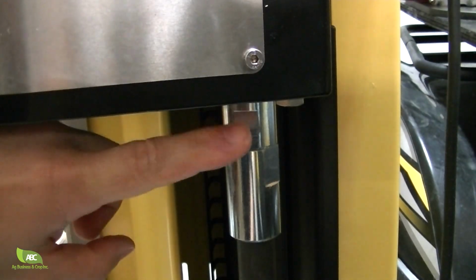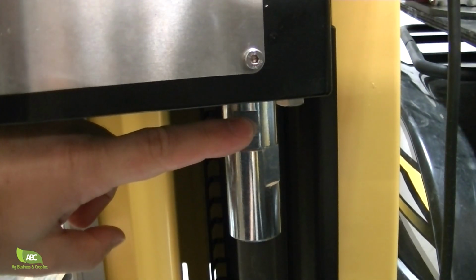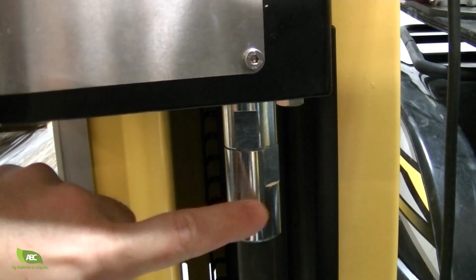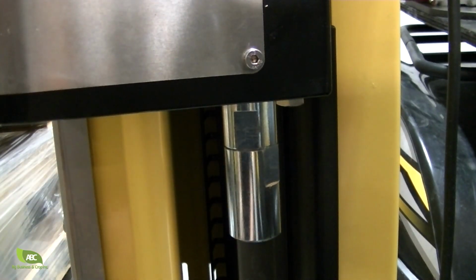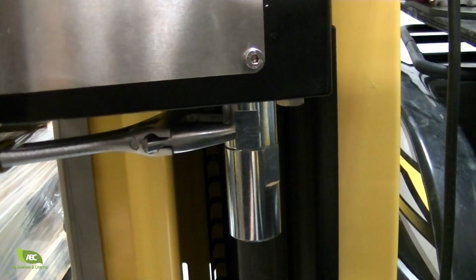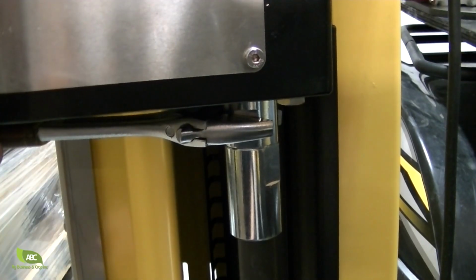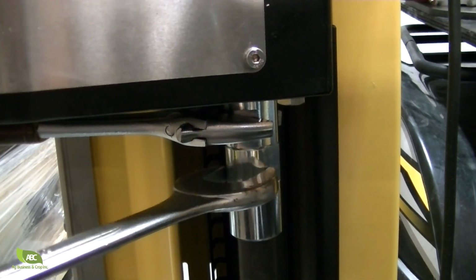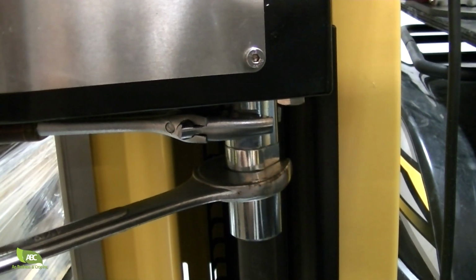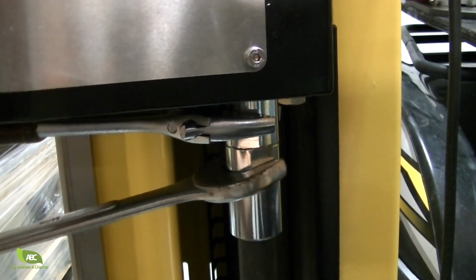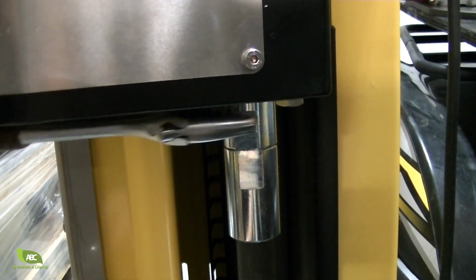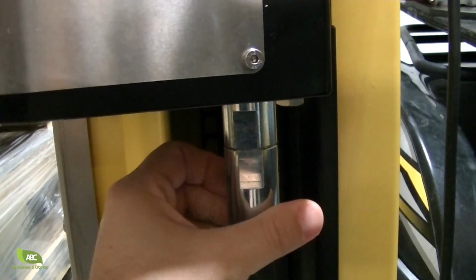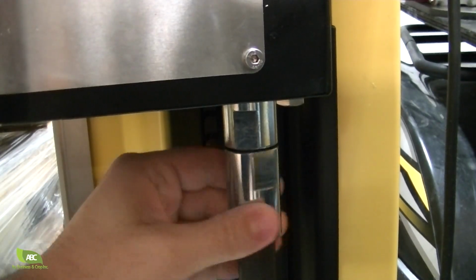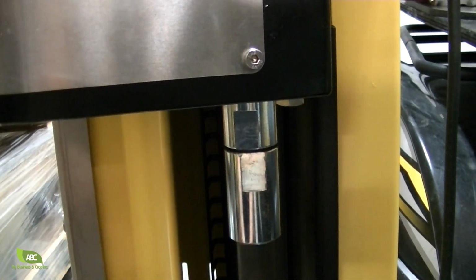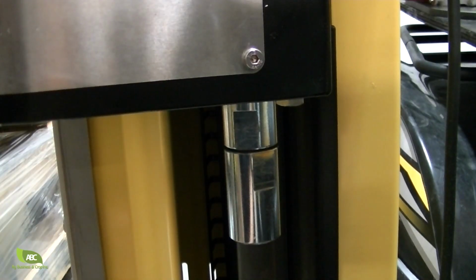You have the probe hub and the probe locking nut. We're going to secure the probe hub in position, and with the second wrench you're going to loosen the probe nut like this. Once the probe nut is loose, you can unscrew all the way and the probe is going to be free to be replaced.